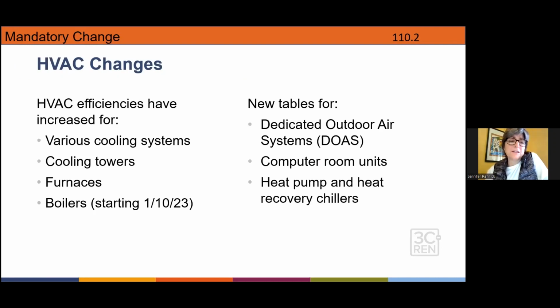So some of those efficiencies have changed for some of the cooling systems, cooling towers, furnaces, and boilers starting in mid-January. And there are brand new tables now for dedicated outdoor air systems. And for those of you who aren't familiar with that, it's essentially a separate small duct system that deals just with the ventilation, fresh outside air. There are now new tables for fan efficiencies for that, efficiencies for computer rooms, electronics, and now heat pump and heat recovery chillers.